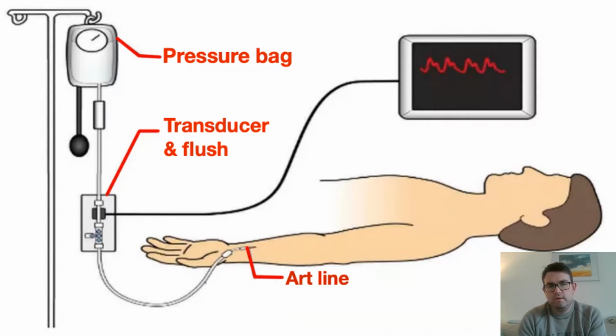Once the arterial line has been sited and we connect it up to the transducer line, we then have the pressure bag inflated, because this column of fluid is under a slight amount of pressure in order to keep everything taut, so that any pulsation then pushes against the transducer and gives us our red wiggly line, as we can see up on the cartoon screen here.